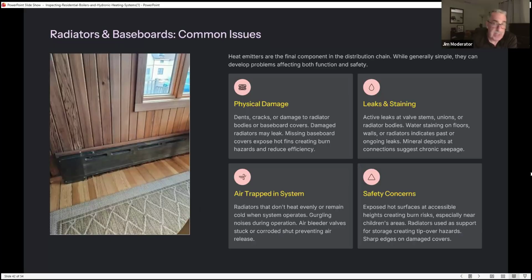Radiators and baseboards, common issues. Heat emitters are the final component of the distribution chain. While generally simple, they can develop problems affecting both function and safety. Physical damage: dents, cracks, or damage to the radiator bodies or baseboard coverings. Damaged radiators may leak. Missing baseboard covers expose hot fins, creating burn hazards and reduced efficiency. You want to look for leaks and staining at the stems, unions, or radiator bodies. You want to look for water on the floor, especially by the legs.